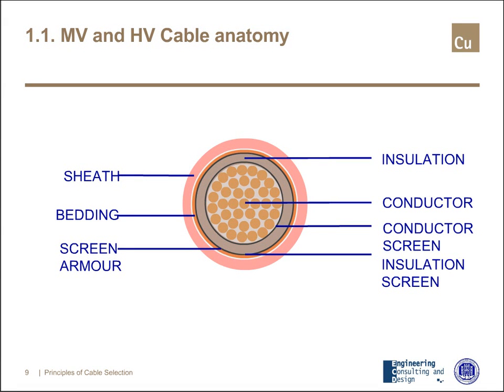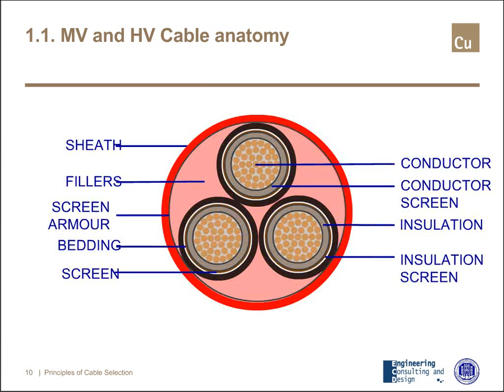Moving to medium voltage and high voltage cables, the structure is still very similar. The core is the conductor. I have the insulation, which plays a much more important role than for low voltage cables. I have a sheath practically every time, a bedding, and I have a screen and an armor. Additionally, I can have a conductor screen and/or an insulation screen, typically made by semiconductive material. This applies to both single-core and multi-core configurations.